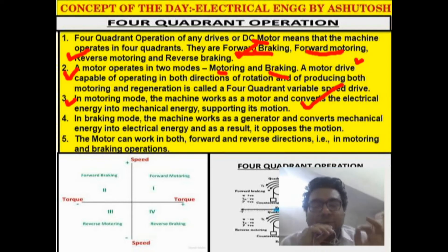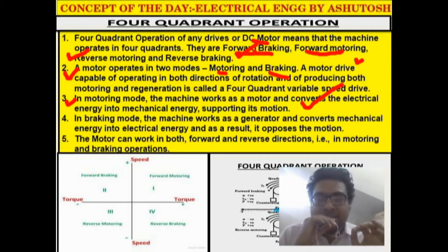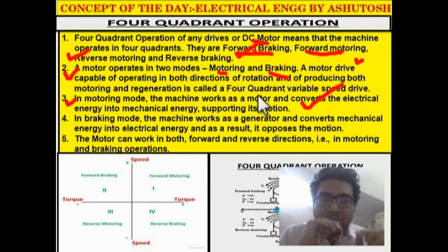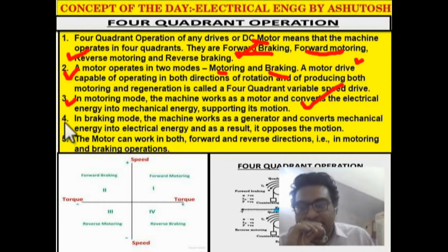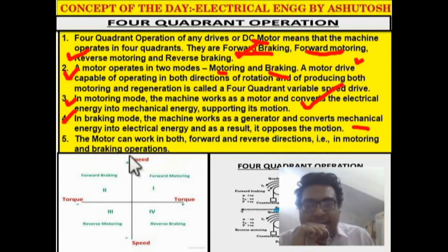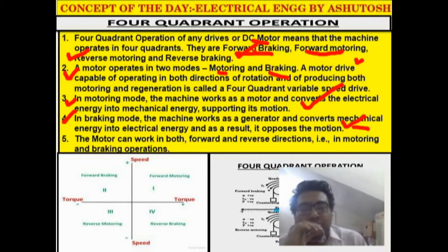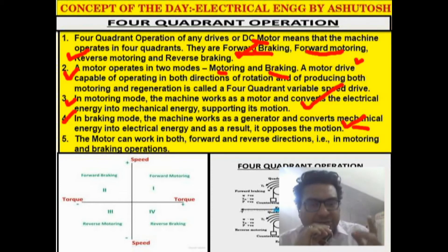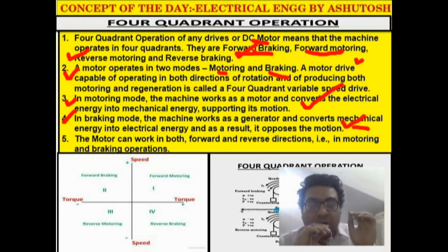This is a very important point: the torque of the motor and the speed of the motor during motoring mode will be in the same direction. In braking mode or generating mode, these will be opposite. In braking mode, the machine works as a generator and converts mechanical energy into electrical energy, opposing the motion.